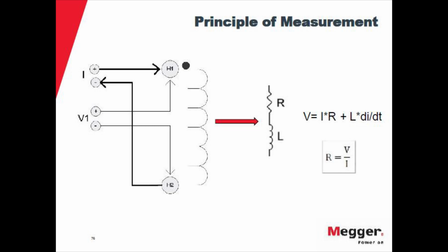That means you need a source that has a very good compliance voltage. And the instrument that we talked about first, the DLRO, has a very low voltage compliance. So there's a very specific instrument to perform the winding resistance test, which is a transformer ohmmeter that has a higher voltage. It has just 10 amps or 50 amps. We have 2 options. And the voltage is much higher than a regular DLRO.